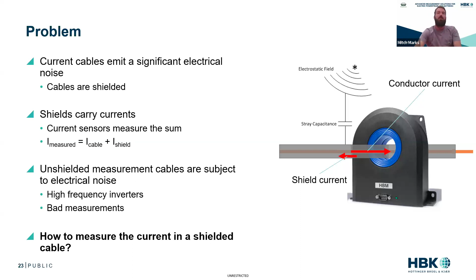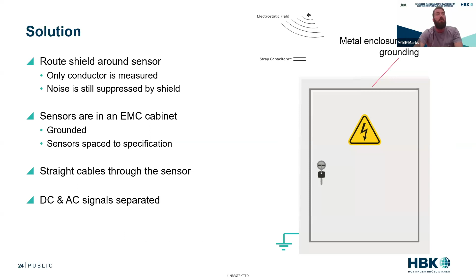The first step is to have a really good enclosure to protect the measurement from EMC. This is a way we can start to clean up our measurements. Inside my cabinet, I want my current sensor with the conductor going through it, and I want to route the shield around the measurement. This allows the inverter to be happy with good shielding and a quality measurement by having just the conductor going through the current sensor. The EMC cabinet protects that measurement from outside EMC, giving us the best measurement possible. Ideally, we'd like to keep our AC and DC signals separate.